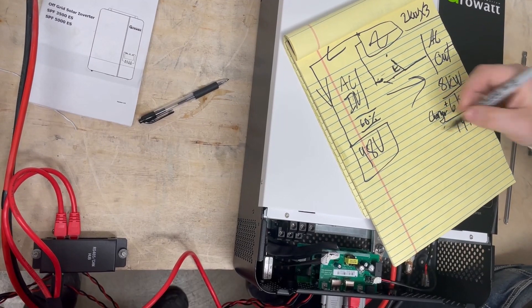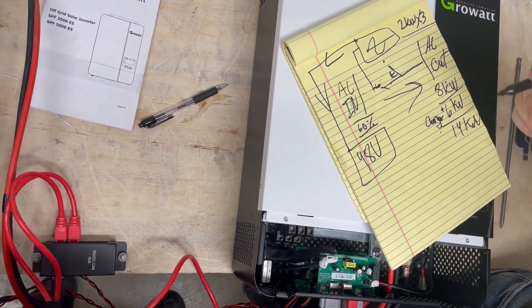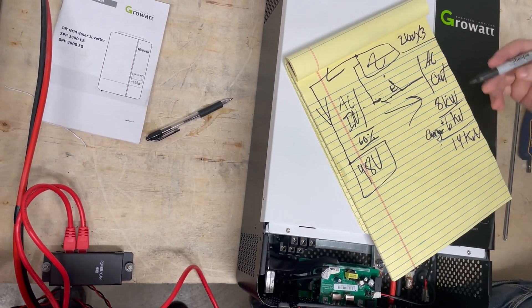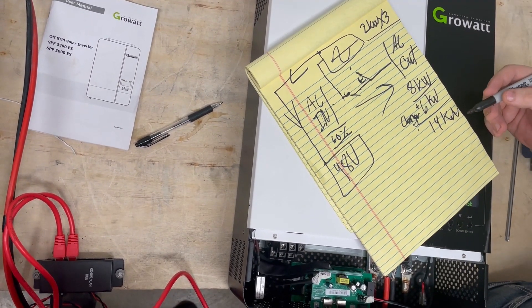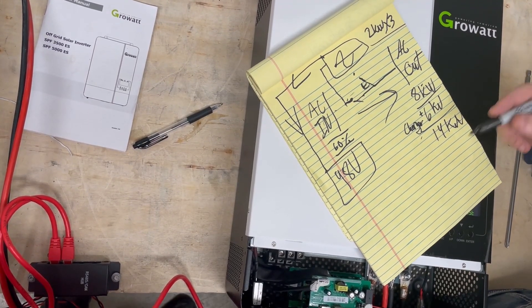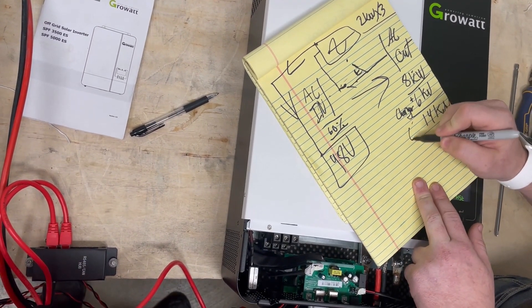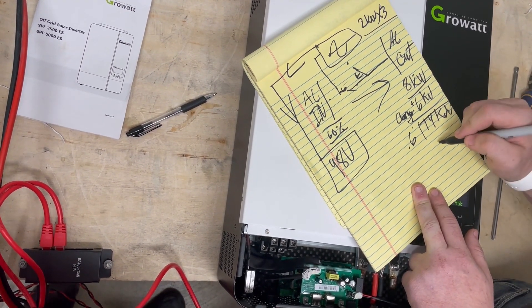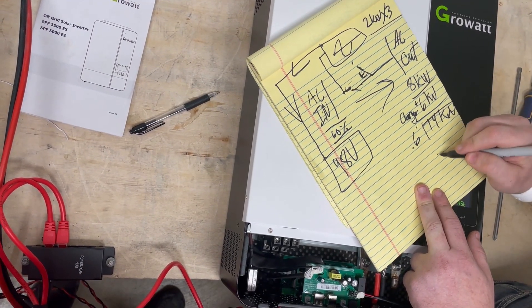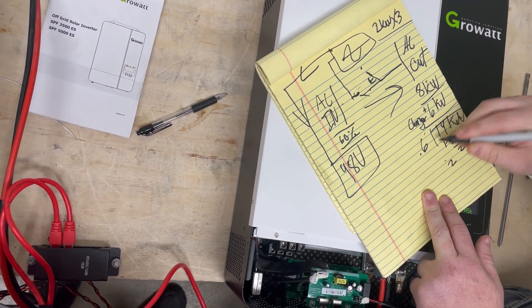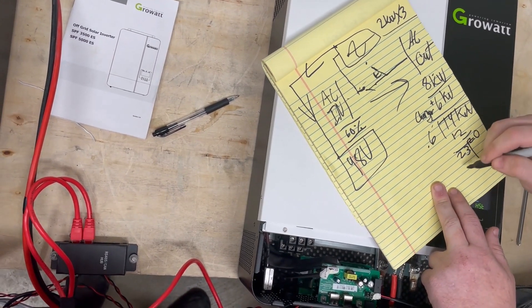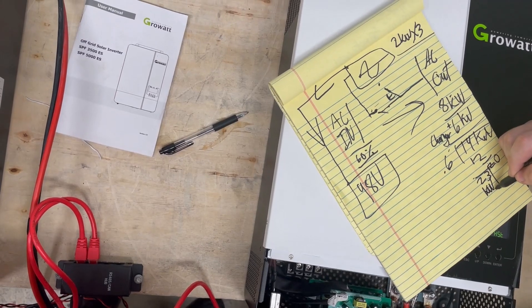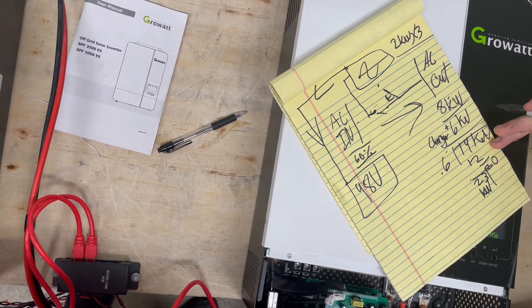So I've got 8 and I'm going to add 6 for the charger and I get 14. Now remember my 60% rule - you can't go over 60% without causing damage to your electronics, including your inverters. So we take 14 and divide it by 0.6. If 6 goes into 14... 2 times 6 is 12, minus 2, 6 goes into 23... so we're searching for 23 kW. You have to have 23 kW to pull this off. So unless you're committed to buying a 23 kilowatt generator, using the inverters as your generator input is not really a good idea.